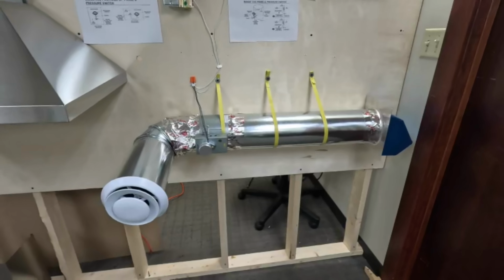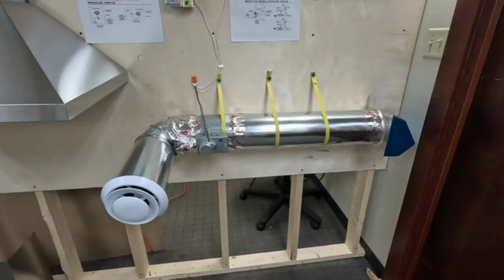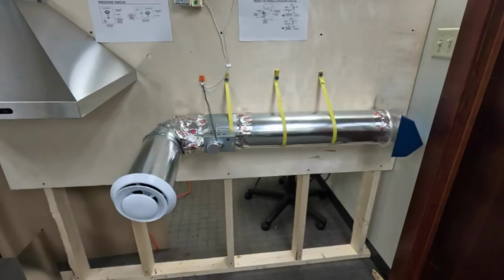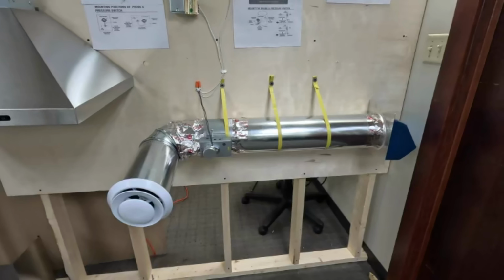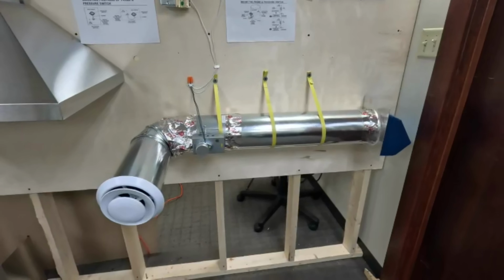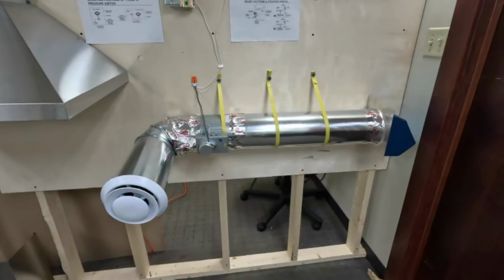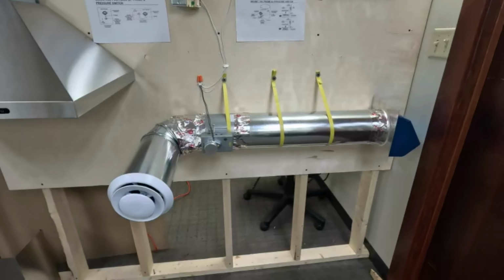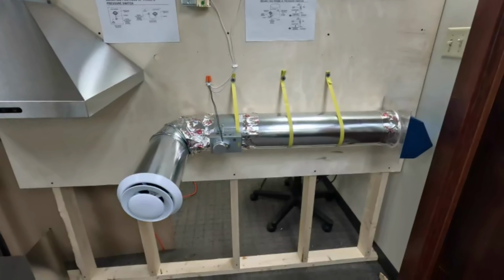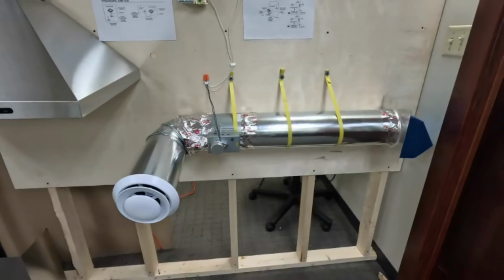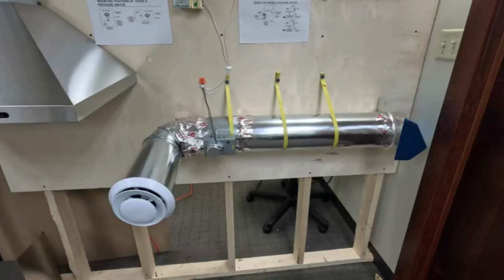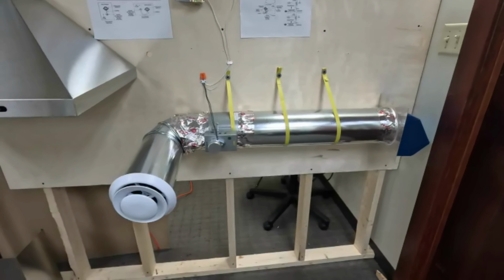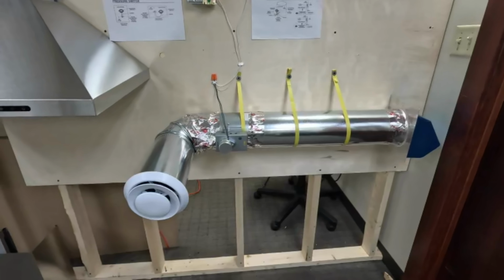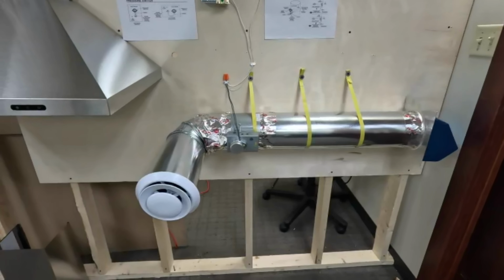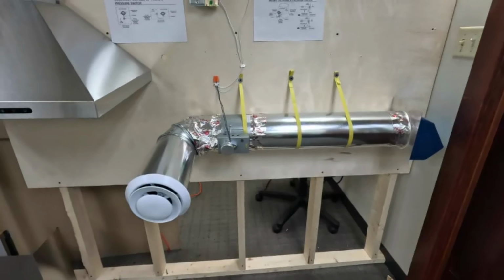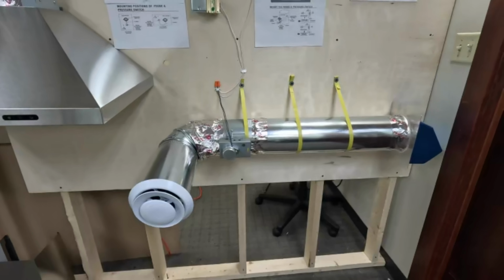Where is the best place to put the makeup air? I get that question a lot, and basically you can bring makeup air just about anywhere in a home, as long as it's not restricted, say a bedroom with a door, or anything like that. The best spot I like is a hallway. At the end of a hallway, you can put a floor register or a wall register. This way, you're bringing air in across most of your home. You're warming that cold air, or cooling that warm air, before it gets to you when you're cooking in the kitchen. I try to avoid gathering places like the living room or any places like that.